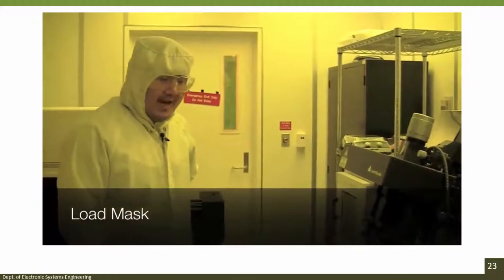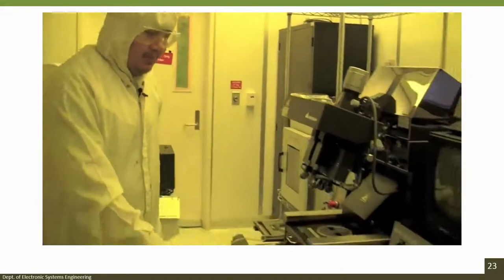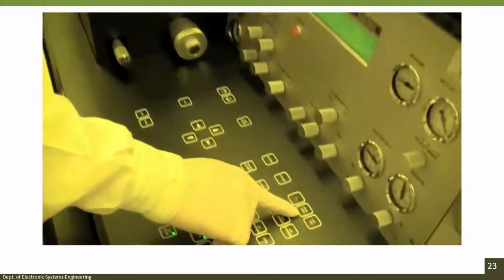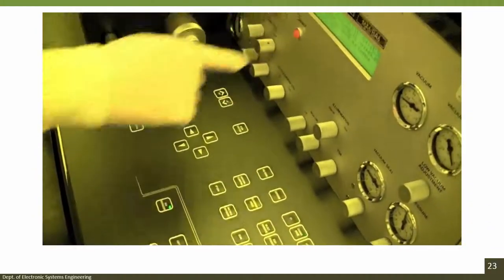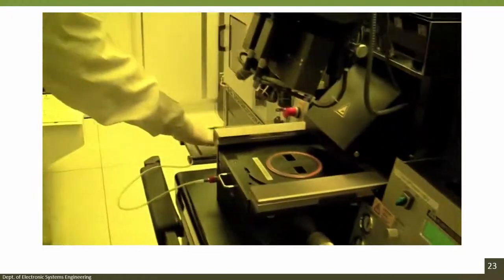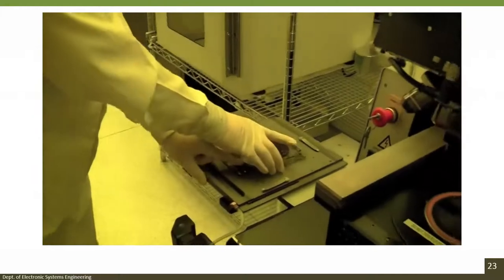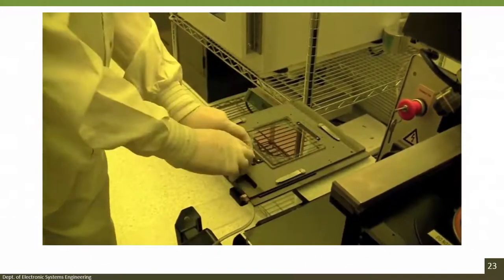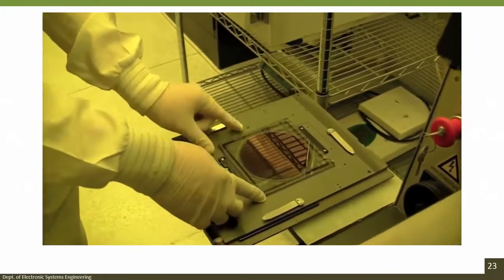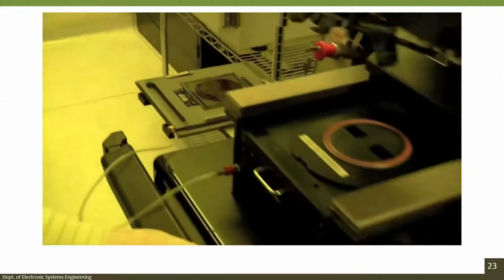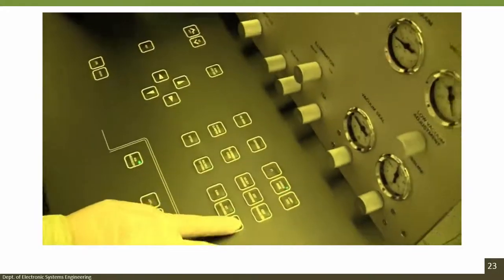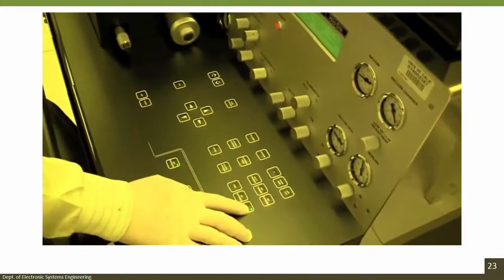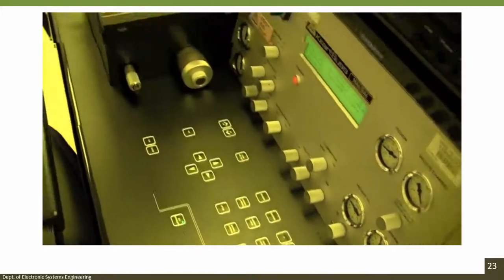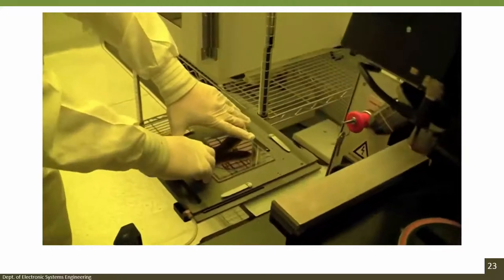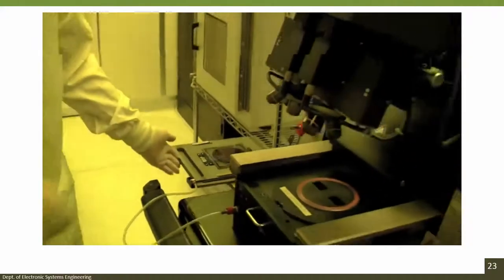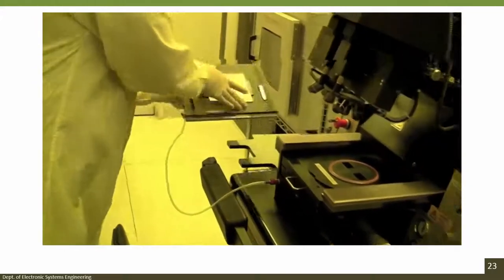What we're going to do now is load the mask. How do we load the mask? We press the button called change mask on the screen. When you hit change mask, you're ready to load the mask. So we put it in here. You load your mask by lifting this clip and putting it in. When it's in nicely, you hit this button called enter, and you can toggle the vacuum. Right now the vacuum is off. When you press enter, now the vacuum is on. When you come back, you can see that it's vacuumed in and it's stuck pretty well. Now we're going to put this in here, so we carefully carry it.